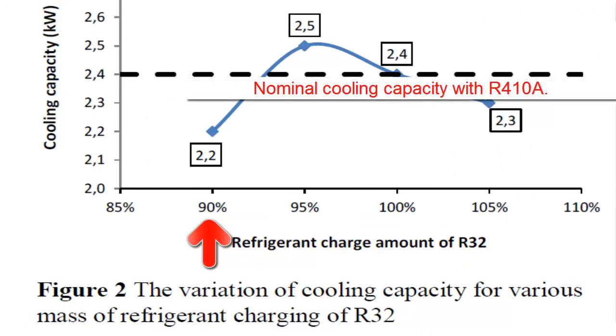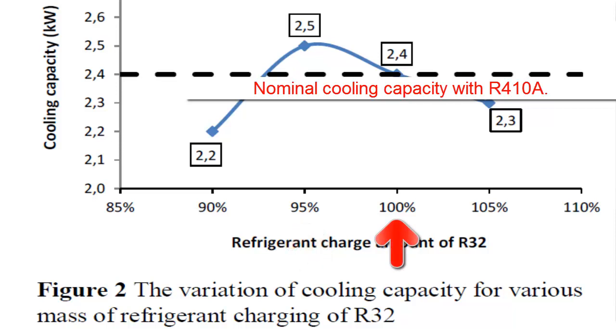3. Cooling Capacity. The cooling capacity provided by the compressor will also be affected by the change from R410A to R32. For instance, as shown in the graph, at a 90% load in grams relative to the R410A charge, there will be a decrease in cooling capacity of around 10%. In the graph example, cooling capacity will drop from 2.4 kW to 2.2 kW. Similarly, at a 95% load, there will be an increase in cooling capacity of about 5%, but with higher electrical current consumption than nominal. At a 100% load, the same cooling capacity as the original equipment will be maintained, but with higher electrical current consumption than nominal. At a 105% load, there will be a decrease in cooling capacity of about 5%, but with higher electrical current consumption than nominal.